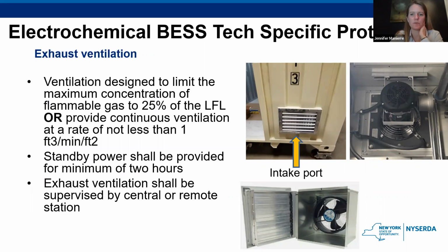All right, so going through each of them in just a little bit more detail, where it applies. The exhaust ventilation is to be designed to limit the maximum concentration of flammable gas to 25% of the lower flammability limit, or some continuous ventilation that's no less than 1 cubic foot per minute per square foot of space. They need to have standby power that will run for at least 2 hours. And this is another one of those systems that needs to be monitored by a central or remote monitoring station where that battery management system is going to be sending signals if something is not working properly.